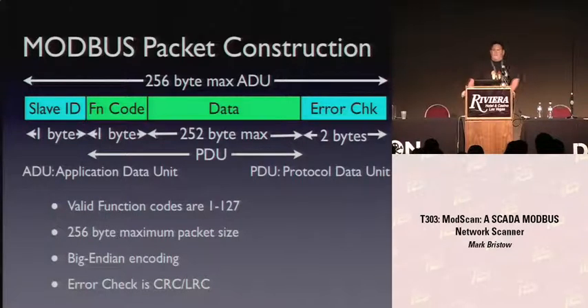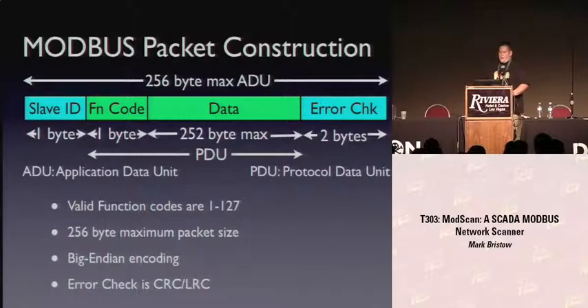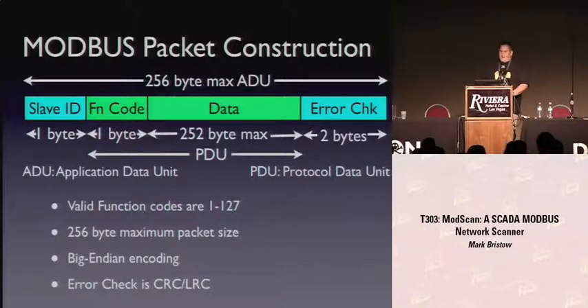Who sees any type of security-relevant stuff in this packet? There's nothing. There's no authentication in here - there's no even place for it. The inherent protocol has absolutely no security. If you're on the wire, you win. You can send commands. Modbus uses a master-slave relationship. Masters don't have to be authenticated, they don't have to authenticate the slaves. You just put out your thing and it happens. So if you make it to the actual wire on Modbus, pretty much the only thing left is you don't know how to address the slaves - and that's what Modscan solves for you.